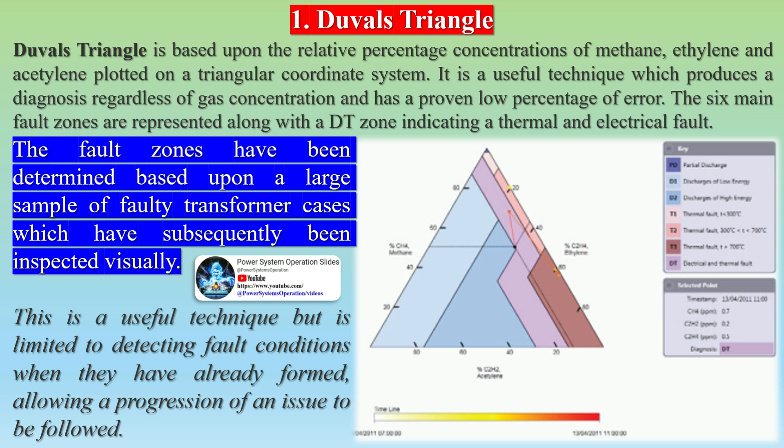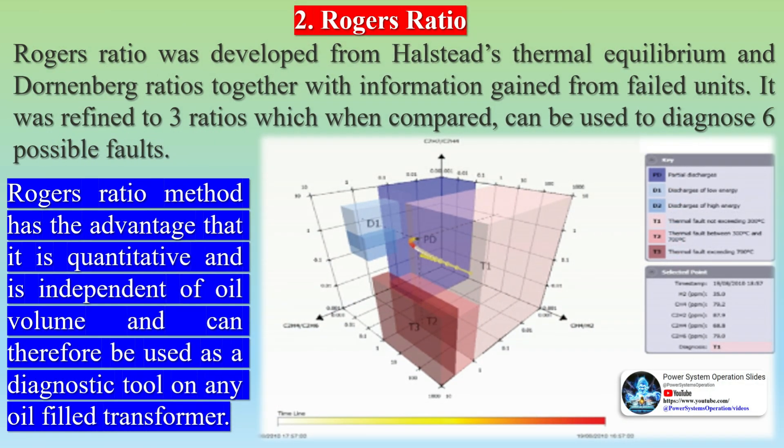As a diagnostic tool, multiple methods of diagnosis have been developed, shown in standards such as IEEE C57.104 and IEC60599, which allow users to relate measured gas-in-oil concentrations to potential ongoing or developing faults. Duvall's triangle is based upon the relative percentage concentrations of methane, ethylene, and acetylene plotted on a triangular coordinate system. It is a useful technique which produces a diagnosis regardless of gas concentration and has a proven low percentage of error.